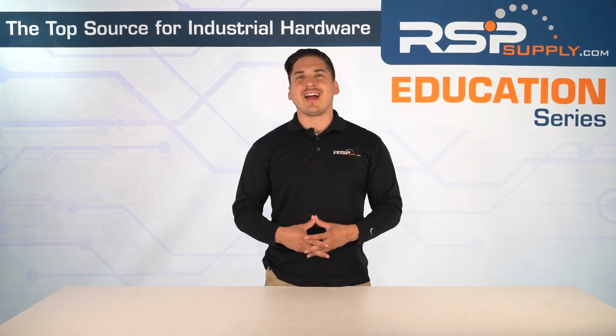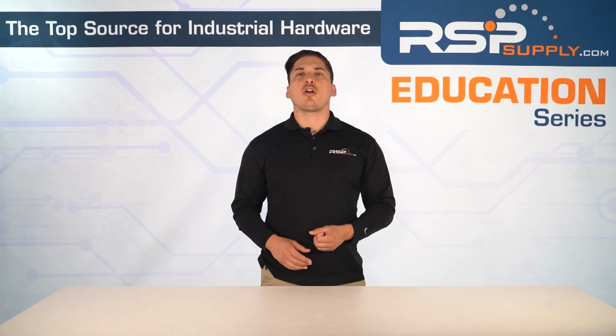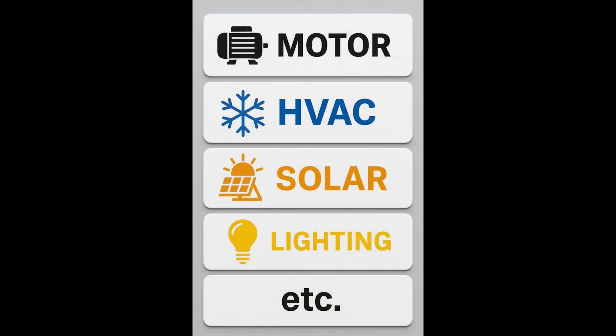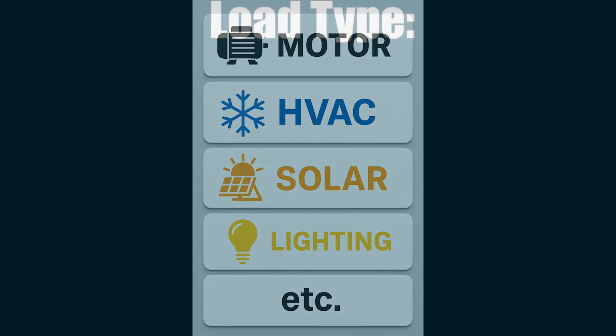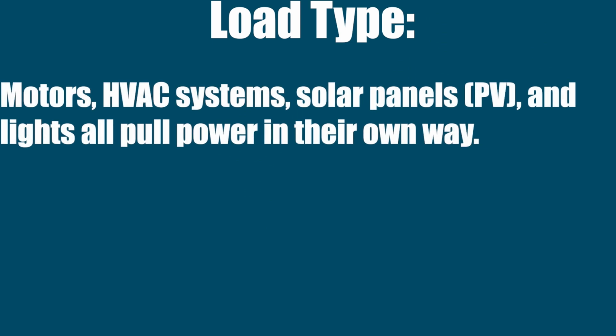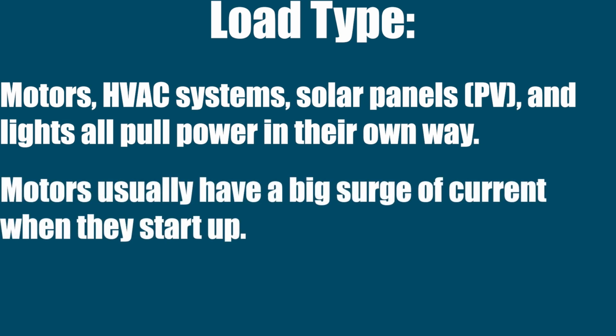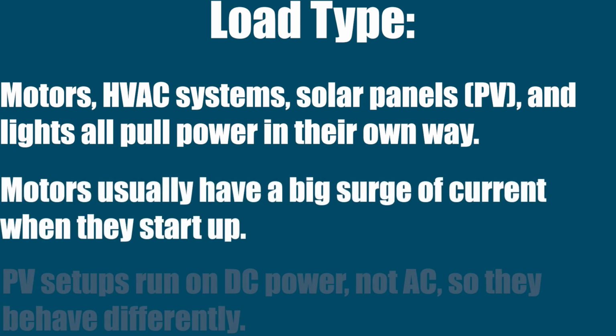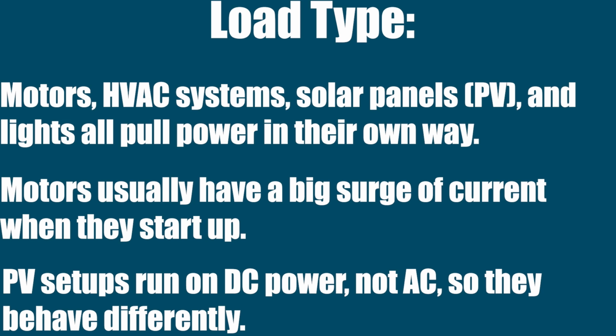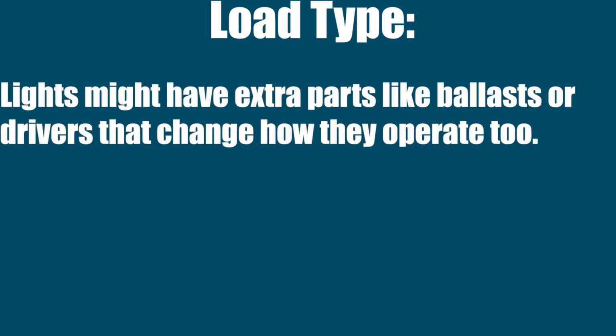So let's start with how to size and select a disconnect switch. You want to start with load type. We're talking whether it's motor or HVAC or solar or lighting, etc. Different types of loads require different kinds of switches. Motors, HVAC systems, solar panels, lights, they all pull power in their own different way. Motors usually have a big surge of current when they start up. PV or photovoltaic solar systems, these setups run on DC power, not AC, so they behave differently. Lights might have extra parts like ballasts or drivers that change how they operate too.